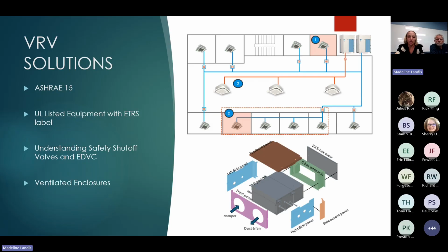What this allows you to do is shut off those valves and limit the amount of refrigerant that goes to each branch, so that if there is a leak, there's a limited amount of releasable refrigerant that would go into those smaller spaces.